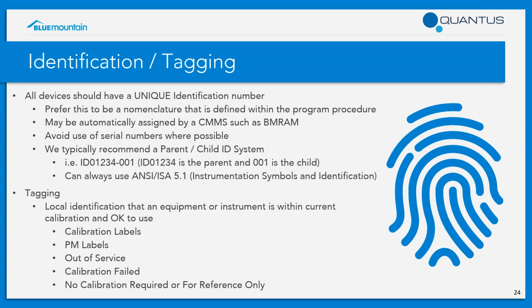And for tagging, for instruments that are in the CMMS and have an ID, you're also going to want to have a defined label on them. Service labels are the most basic identification of tagging. If an instrument requires routine service, it should always be tagged with its status, and this would be your CAL or preventative maintenance label. If that device were to fail calibration or be out of service, you're going to want to be able to label it as well and have those labels defined within your CMMS, your calibration and maintenance management program, so that in this event, people know what to do and they can tag the instrument with a status so nobody uses it. And of course, if we have calibration not required or for reference only, we're also going to want to take a little time to identify those.